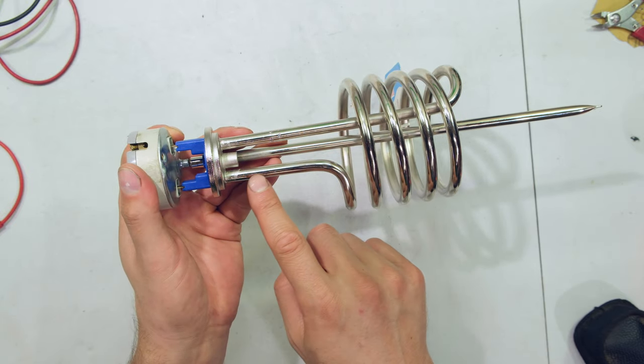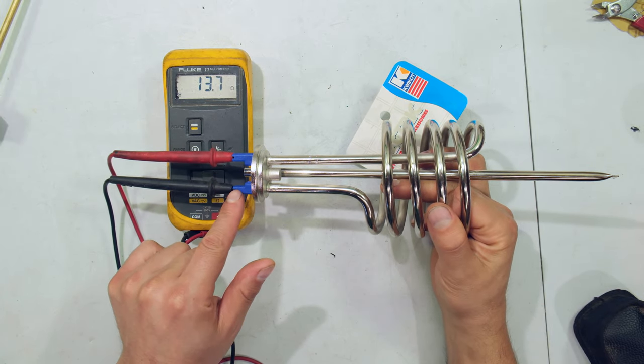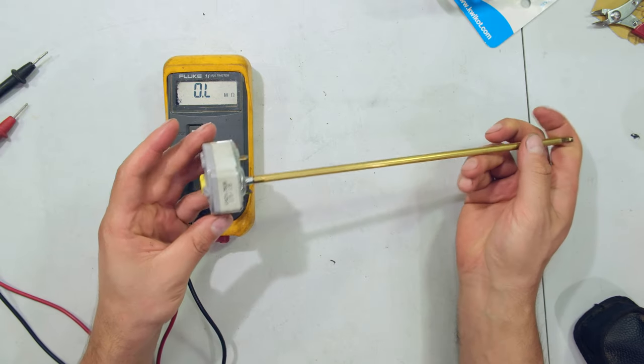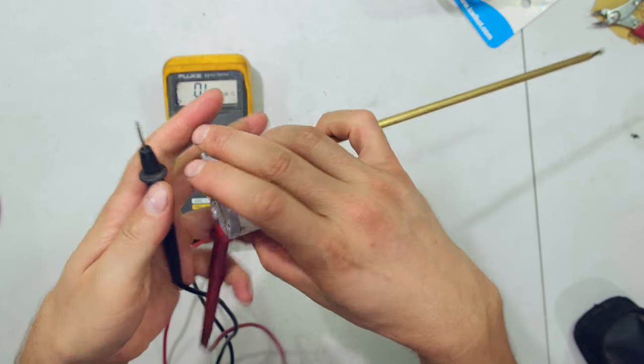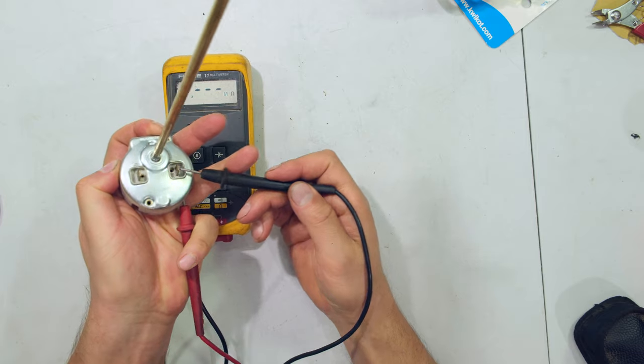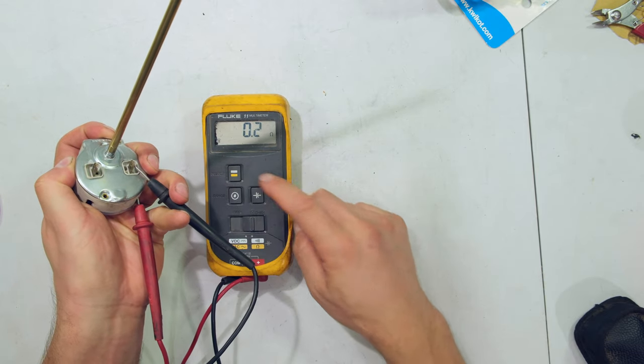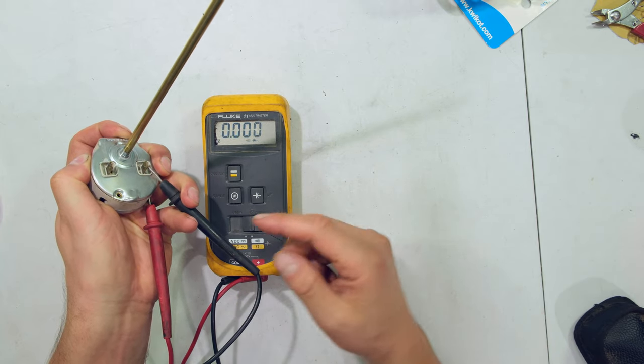So this is a resistive element. Looking at the resistance of the element, you can see that it is 13.7 ohms. The thermostat operates as a switch, so what that means is if I put my lead over here on the neutral and then I put my other lead over here on this terminal, it's a very low resistance there - 0.2 ohms. So if I do a continuity measurement, you can see it's zero and hear the beeps. Continuity measures a short circuit, so we can see that from the neutral terminal...